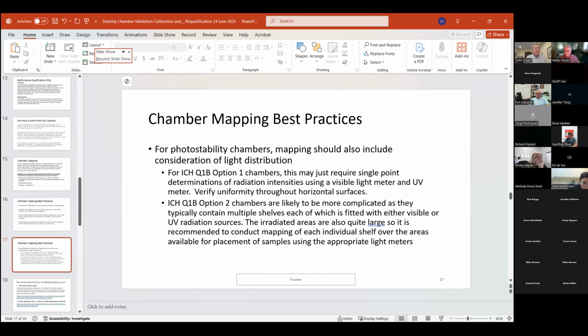And also, having your instruments calibrated, you can send them frequently back to the manufacturer for calibration. And it's been discovered that if you take the same instrument and send it to two calibration sources, they might come back quite different from each other. So it's a process in development, but I think the longer we have photostability chambers, the better the technology will become for that.